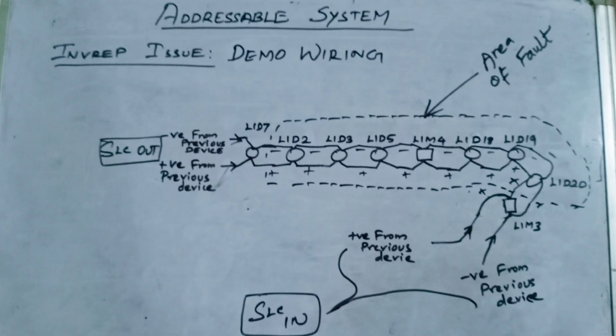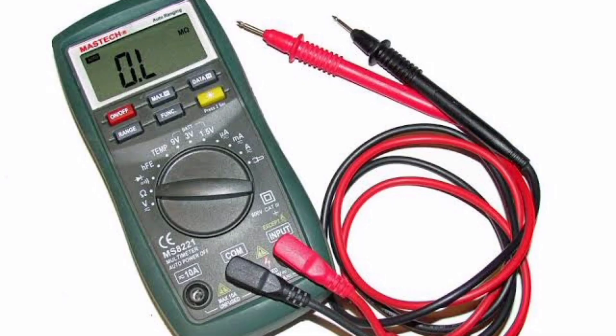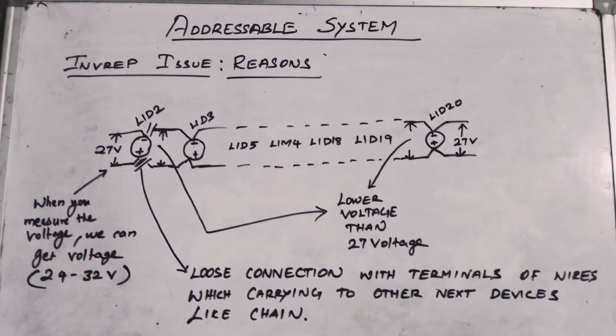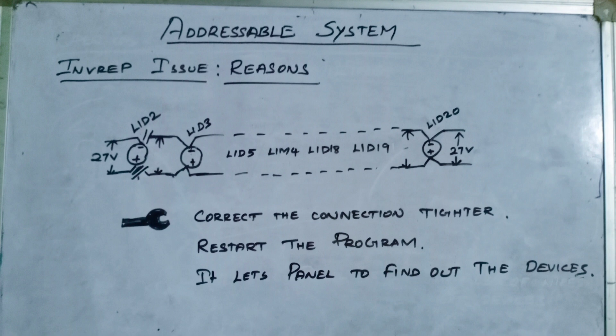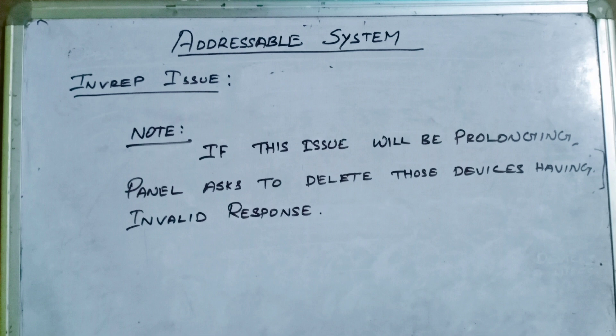Invalid response can happen because of loose terminations in the devices. Normally, a device should take the SLC voltage between 24 volts to 32 volts and deliver the same to other devices. If any device takes the SLC input at the appropriate voltage but delivers lower voltage to other devices, those downstream devices will not communicate with the panel. Go to the first device shown on the panel display, check the wiring termination, clear the trouble, and restart the panel.